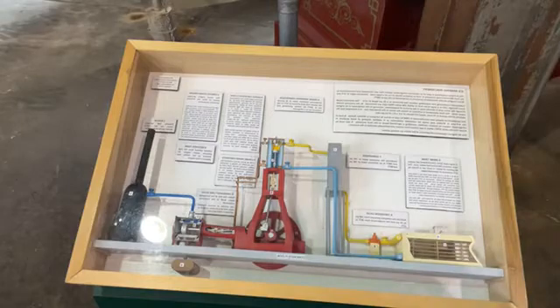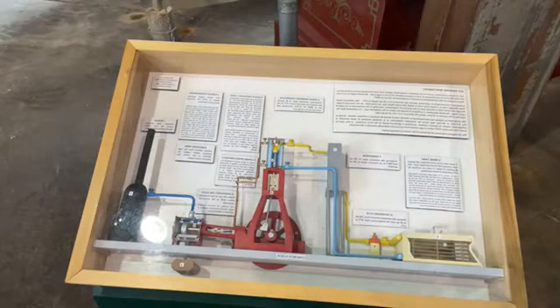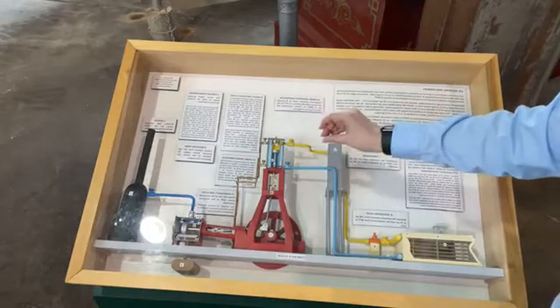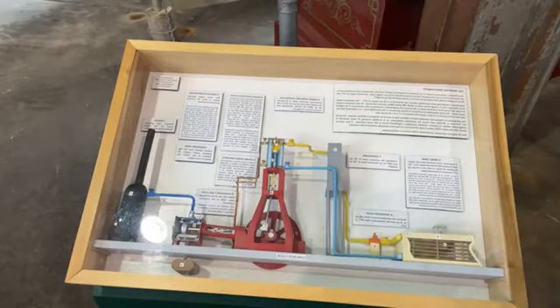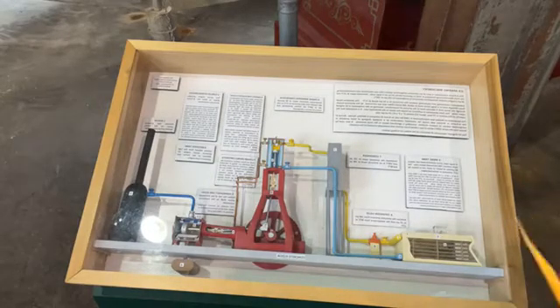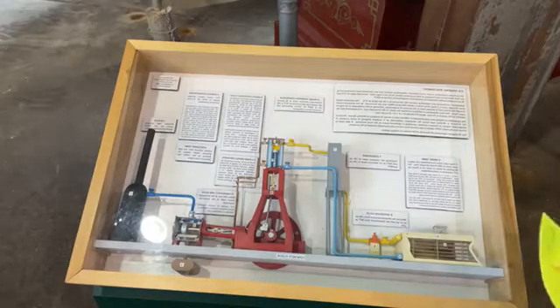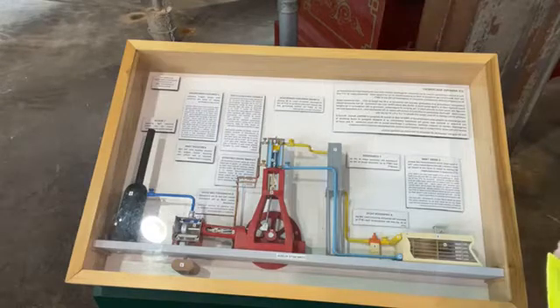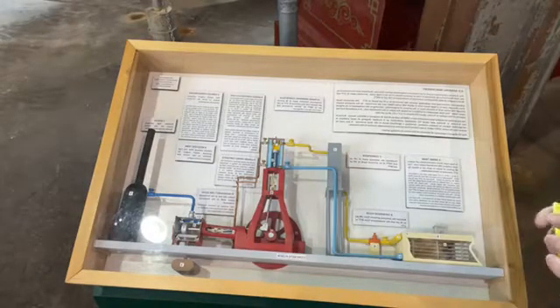The process of refrigeration has four basic steps, and refrigeration is actually just a transfer of heat — we're not adding cold to anything, we're removing heat through different steps throughout the machine. So we have the ammonia compressor cylinder. When you compress something it creates pressure and increases the heat and temperature, and what our machine wants to do is reject that heat. We're changing the ammonia from the state of liquid to gas and then back to liquid. Ammonia boils at negative 28 degrees Fahrenheit, so we don't need a whole lot of temperature difference — hot and cold are very relative. The piston in the chamber increases pressure and temperature.